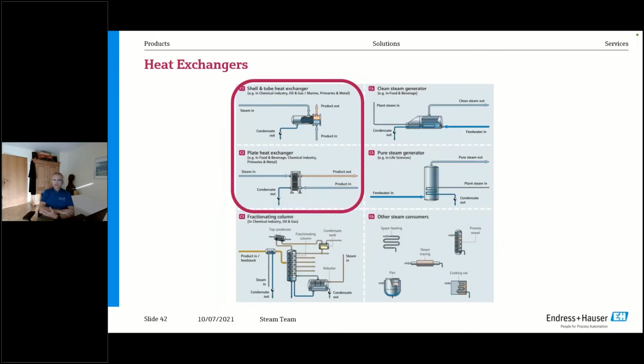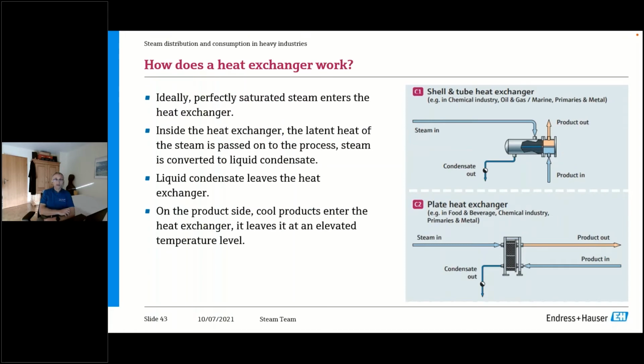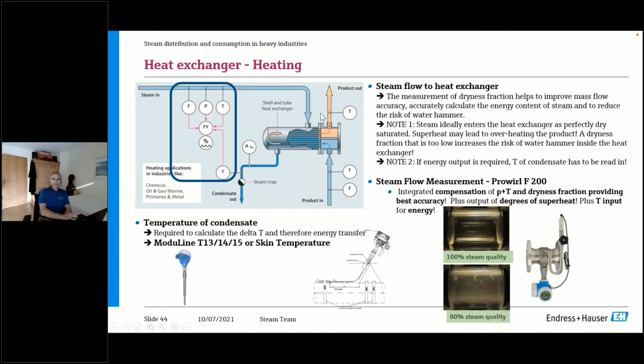And typical heat exchangers, there's a variety out there. You find very often the shell and tube heat exchangers in the process industries, plate heat exchangers too, depending on the cleanliness of the fluid. So plate heat exchangers are also very common, by the way, in the cleaner industries. So ideally, in both cases, you have perfectly saturated steam entering here. This is ideal. Reality, however, is you have superheated steam or wet steam. So you have neither. Therefore, it's very good also here to know what is exactly the energy content of my steam.